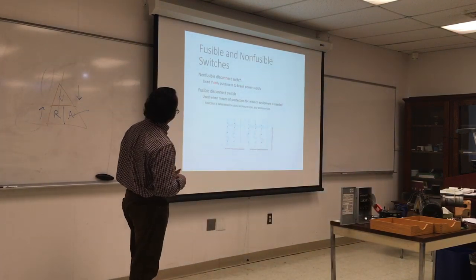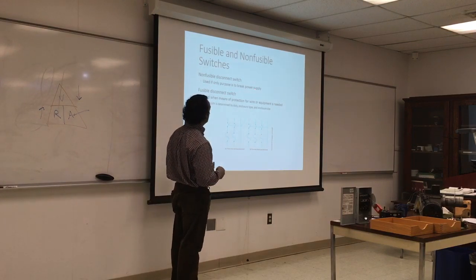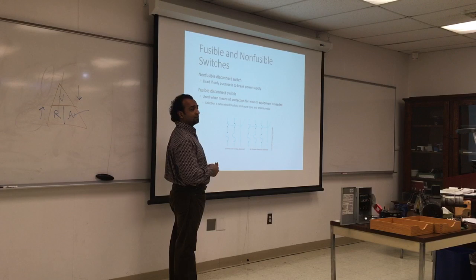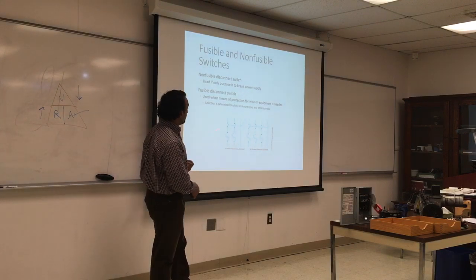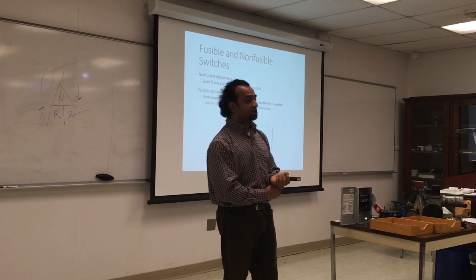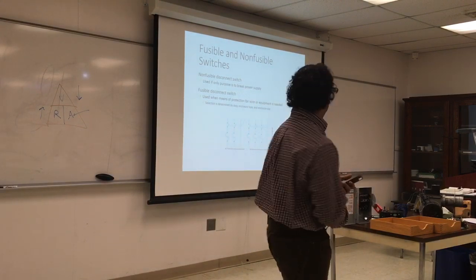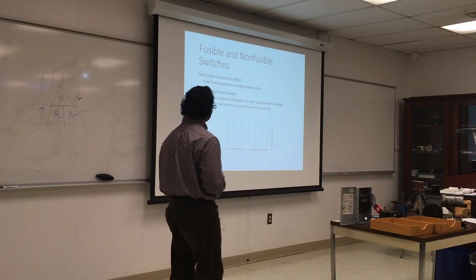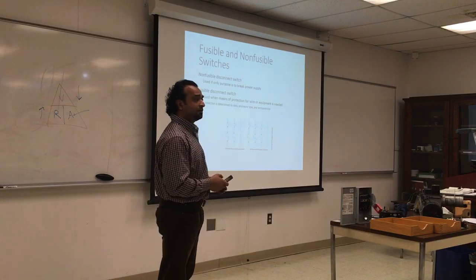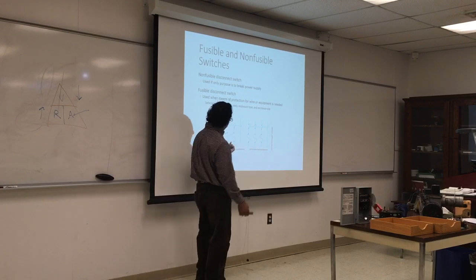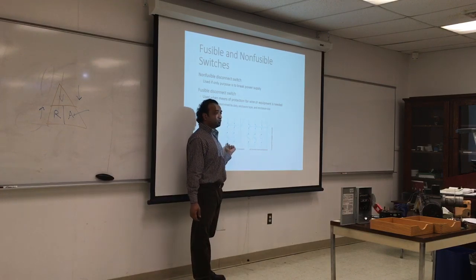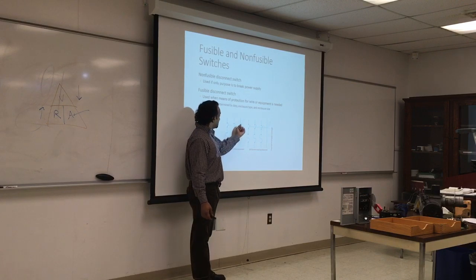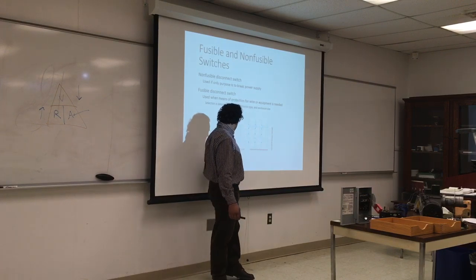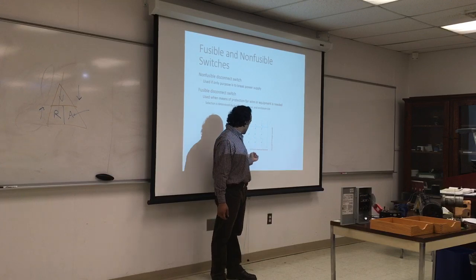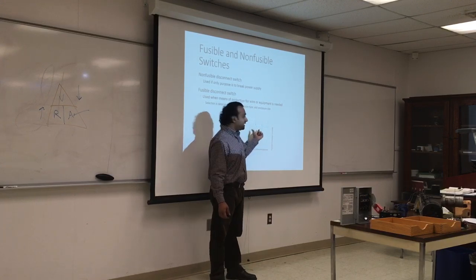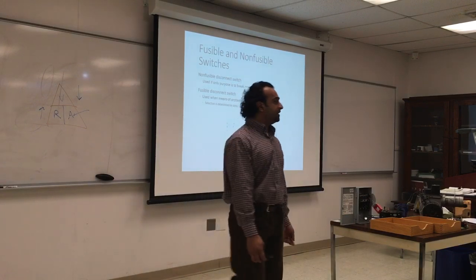Fusible and non-fusible. A non-fusible disconnect switch is used normally to break the power supply. It doesn't do anything besides that, just on and off. The fusible ones have fuses, so they can also act as power protection in case there is a surge or overload of power. Questions so far? So these are fuses, and these are for the hot line. So probably this is 240, 110 and 110, and this is my neutral. And this is a three wire, two fuse disconnect. This is the 4 wire, 3 fuse disconnect. So it probably is 3 phase.